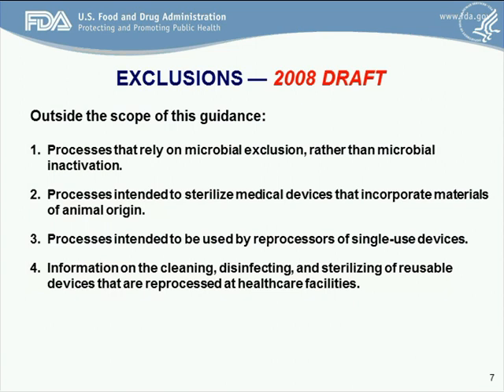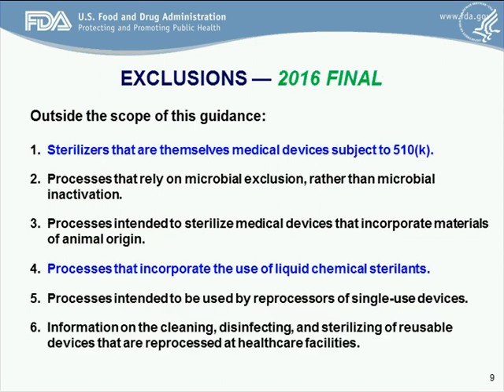Based on public comment resolution, we actually wound up adding two additional exclusions. That includes sterilizers that are themselves medical devices subject to 510K review, and processes that incorporate use of liquid chemical sterilants.